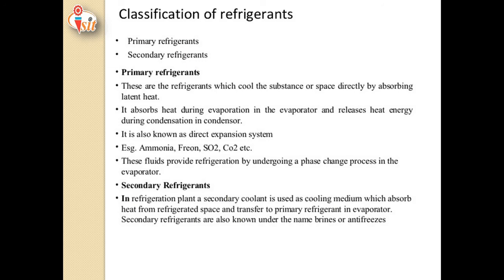This high-pressure, low-temperature liquid refrigerant then flows through the throttle valve or expansion valve, where pressure drops considerably, producing low-pressure, low-temperature liquid refrigerant. It finally flows through the evaporator where it absorbs heat during evaporation. That is why primary refrigerants are also known as direct expansion systems. Examples of primary refrigerants include ammonia, Freon, sulfur dioxide, and carbon dioxide. These primary fluids provide refrigeration by undergoing a phase change process in the evaporator.